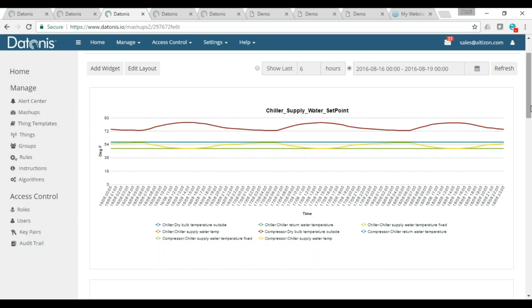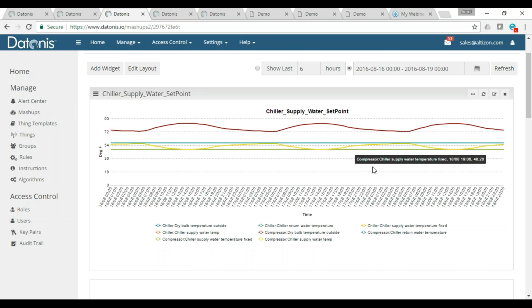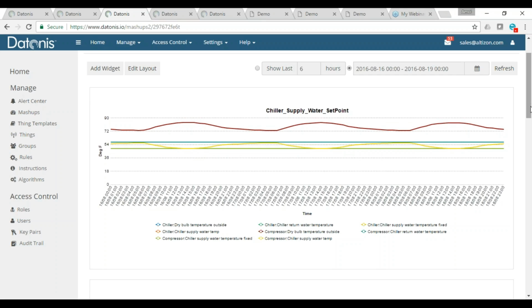What you see on screen is simulated data over a time period, where the chiller water supply temperature and set point vary based on the actual load of that zone. The idea is that with a change in load, the chiller supply water set point changes so the comfort level of that zone is maintained.